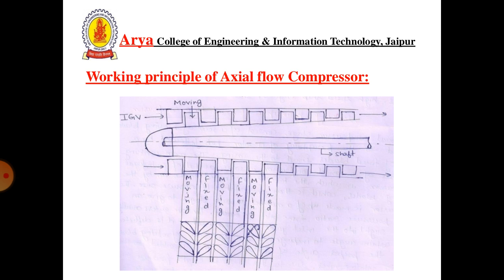The air enters axially from the left into the inlet guide vane, from where it is deflected by a certain angle to impinge on the first row of rotating blades with the proper angle of attack. Kinetic energy is added to the air by rotating blades, causing a slight pressure rise. The air is discharged at a proper angle to the first row of stator blades, where the pressure is further increased by diffusion. The air is then directed to the second row of moving blades, and the same process is repeated for remaining stages.